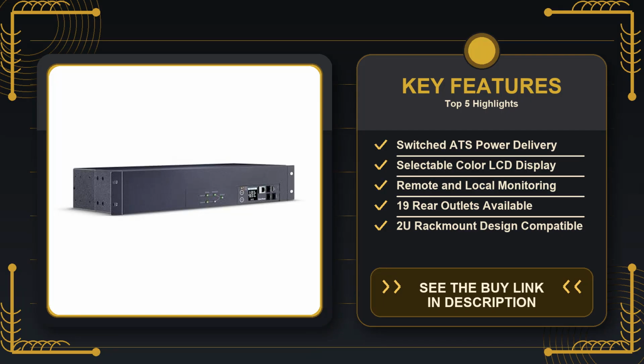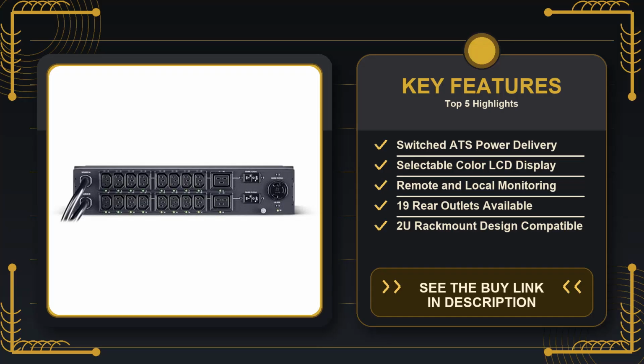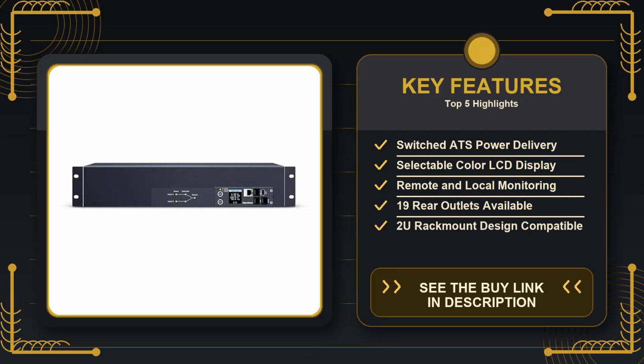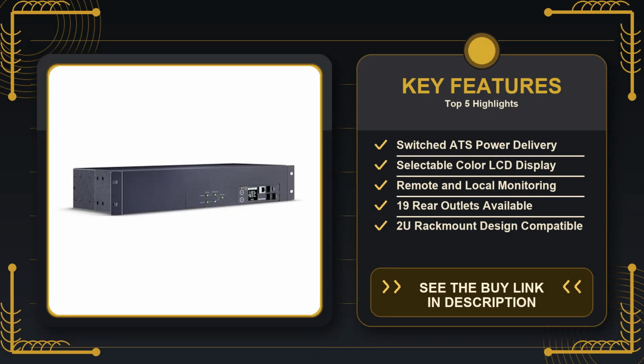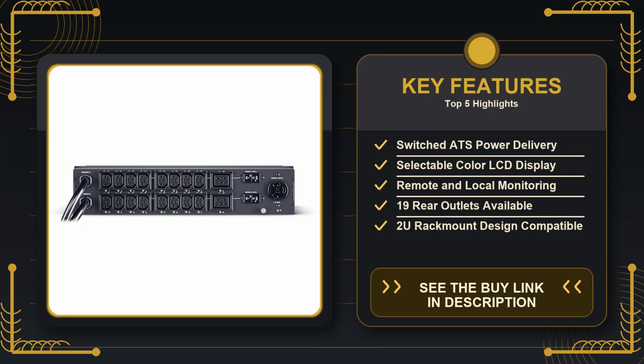What really sets the switched part of this PDU apart is the ability to control each outlet individually, either locally via the front panel or remotely through network management. The LCD panel is not just a static readout, you can cycle through voltage, current, and load percentages, and you can set thresholds that trigger alarms if an outlet starts drawing more than it should.